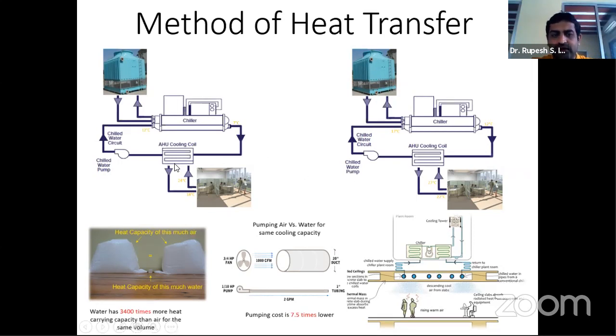This is a classic plant. This is a normal chiller plant, which all of us have probably used at some point of time, where my chiller outlet would be 7 to 8 degrees Celsius and my inlet would be somewhere about 12 to 13 degrees Celsius. And my room conditions at 24 degrees would have an AHU cooling coil getting in water at about 12 degrees and then pushing it out at about 13 to 14 degrees Celsius.